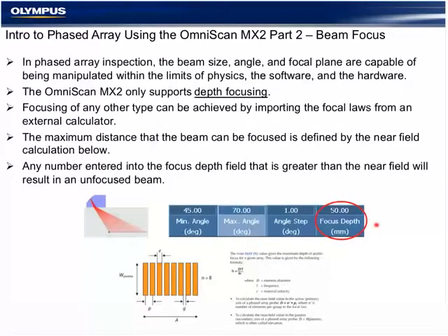This focal depth is limited to the mathematical near field of the probe and wedge, which is available in the NDT SetupBuilder or typical beam plotters like the ES beam tool as well.